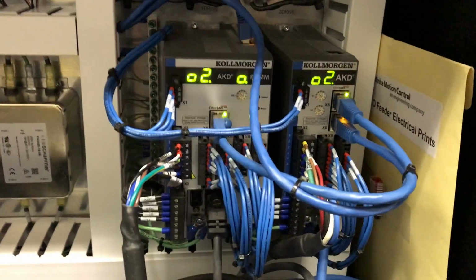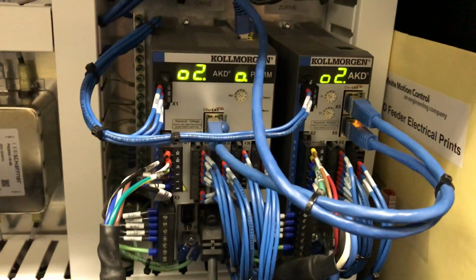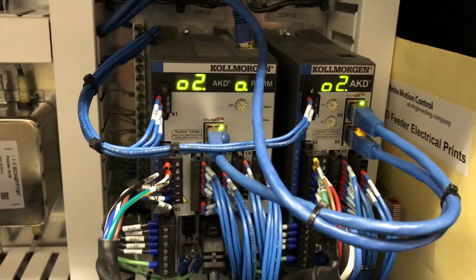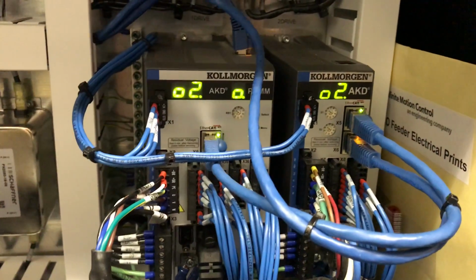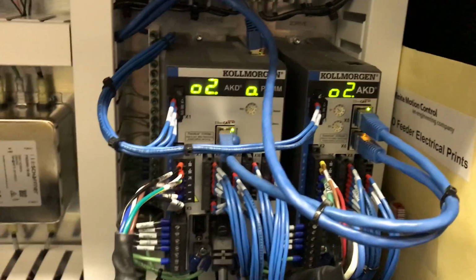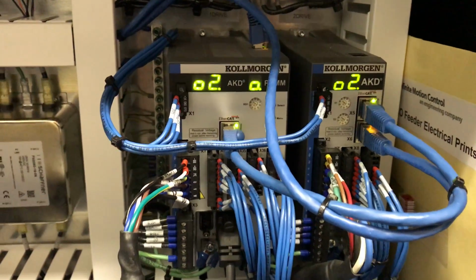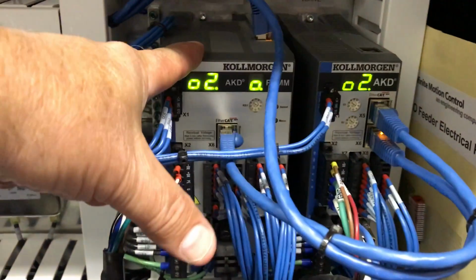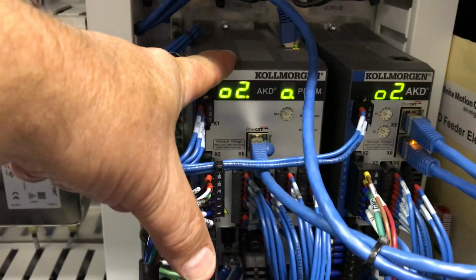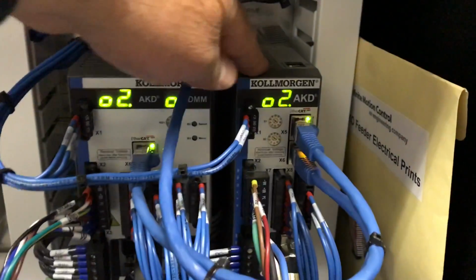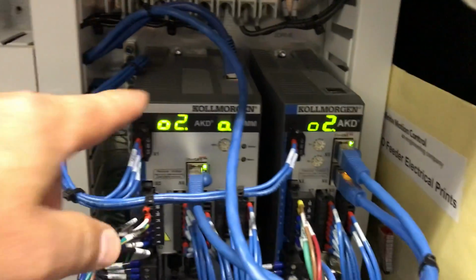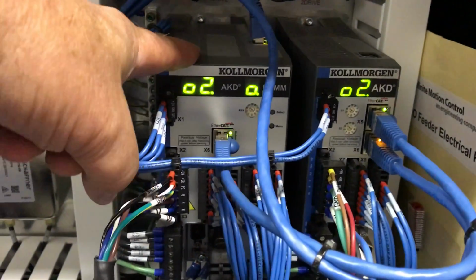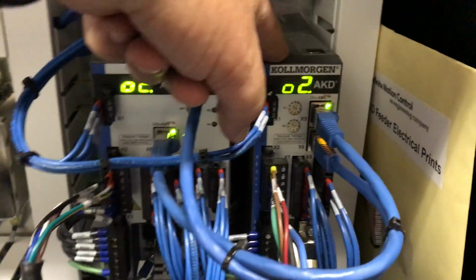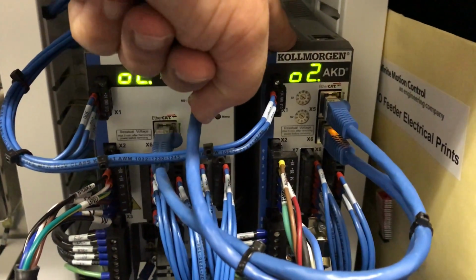This video discusses the fault codes, error codes, and warning codes that are displayed on the Kollmorgen PDMM drive and the slave drives. So this is a board feeder. This is the PDMM drive. This is the drive that has the program running in it. This is a slave drive to the PDMM. So in this machine, this is operating the horizontal servo. This is operating the vertical servo.